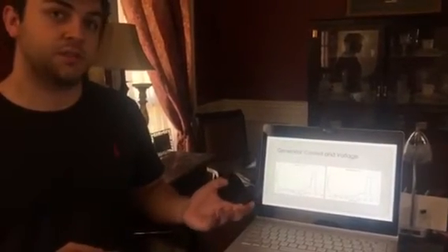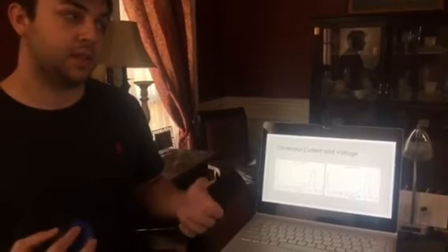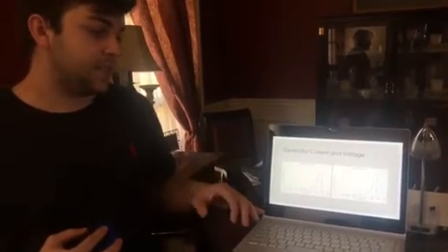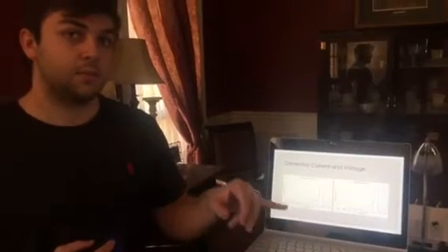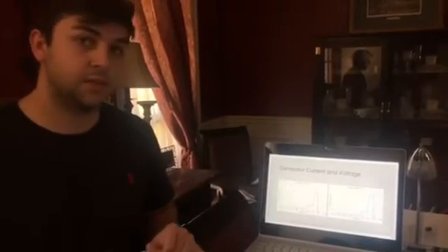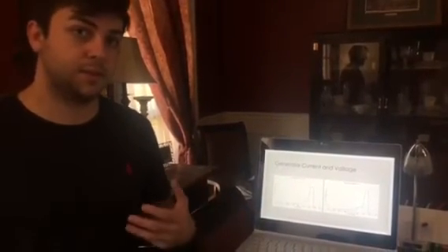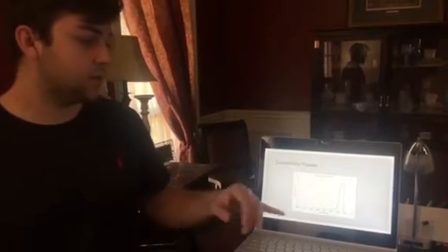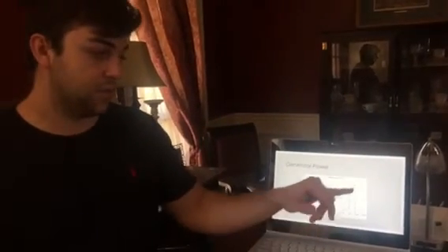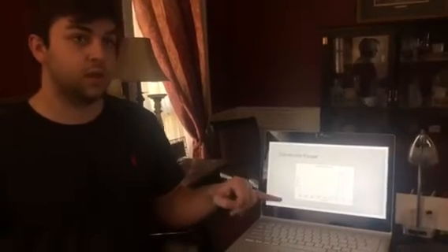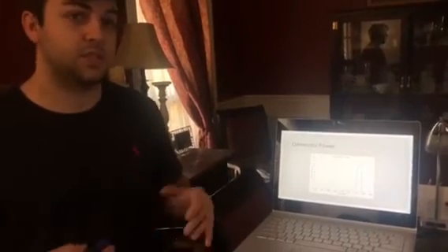Current and voltage generation within the alternator, the exciter. We can see that these graphs will look very similar due to the fact that they're proportionally related. Power is going to be square root of 3 times voltage and current. So our graph would look very similar to those two, just multiplied by a magnitude value, which is that square root of 3.